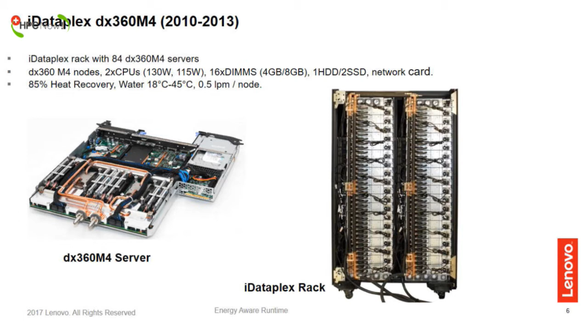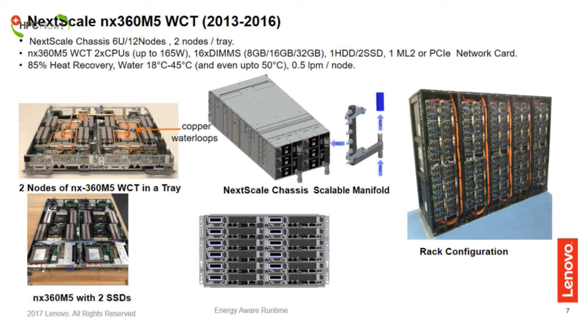With the second generation, which is the NeXtScale, it's been much more modular. So we have a scalable manifold. You can have a non-direct water cooled chassis in the rack. And then, of course, one of the major things is to reduce the cost, because the added cost of the water cooling can be a good reason not to install it. So we did a lot of work on reducing it. We installed LRZ phase 1 with iDataPlex, phase 2 with NeXtScale, 9,000 nodes, 3,000 nodes.